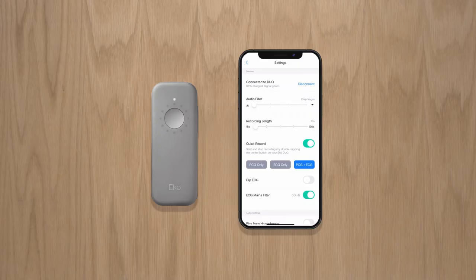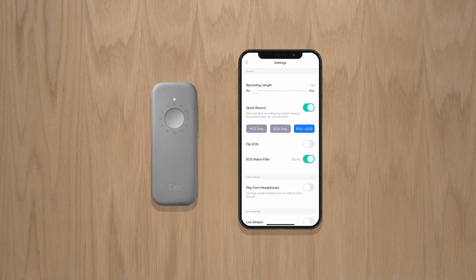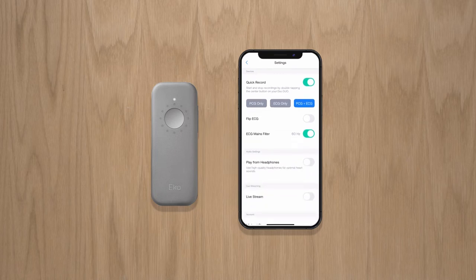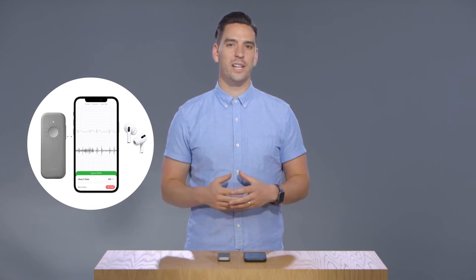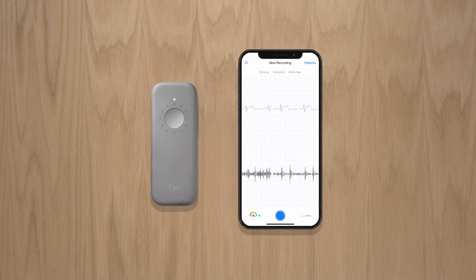To review and adjust your settings, open the menu on the upper left side of the screen. Here you can view the battery percentage for your Duo, change the audio filters, adjust recording length and more. You can also activate Play From Headphones, which allows you to listen to auscultation sounds from your connected headphones rather than the Duo earpieces. Click the arrow to return to the visualization screen.